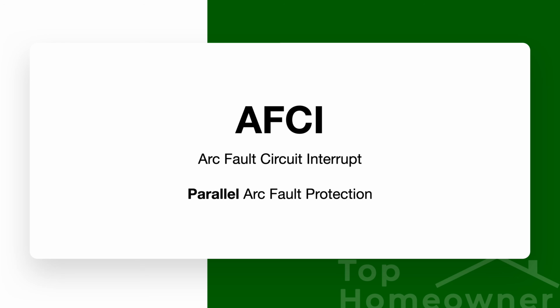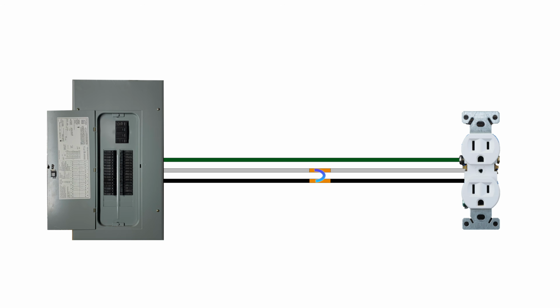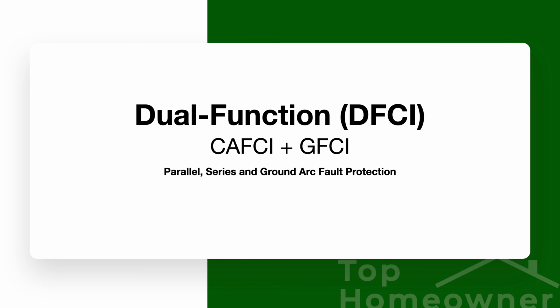Another more advanced type of breaker is called AFCI, and that protects against something called arc faults. So an arc fault is basically when a wire shorts out and it causes some sparking. There's also something called DFCIs. So DFCI is a combination GFCI and arc fault or AFCI breaker. And so on those breakers, it could be anything from a standard overload to a ground fault in a bathroom or to an arcing situation. So you really need to troubleshoot and figure out exactly what's going on.